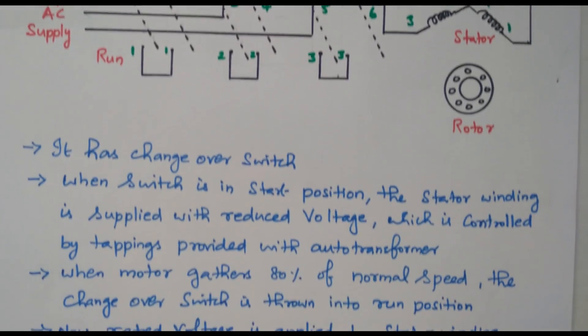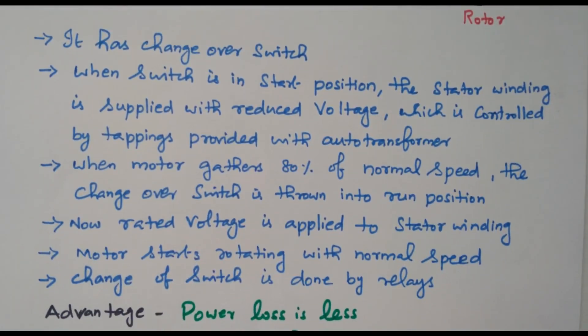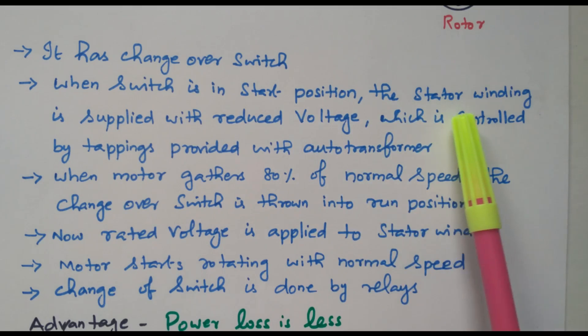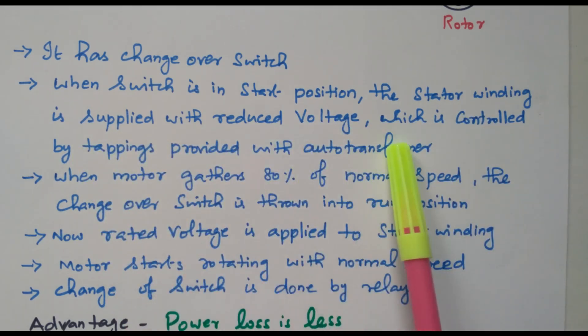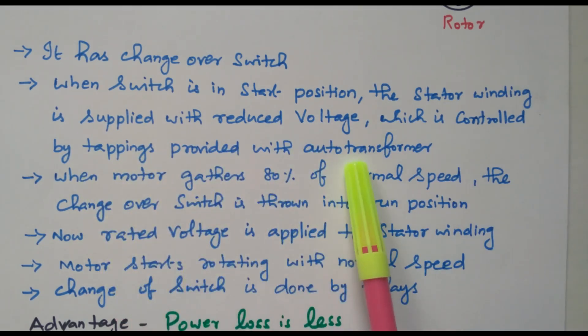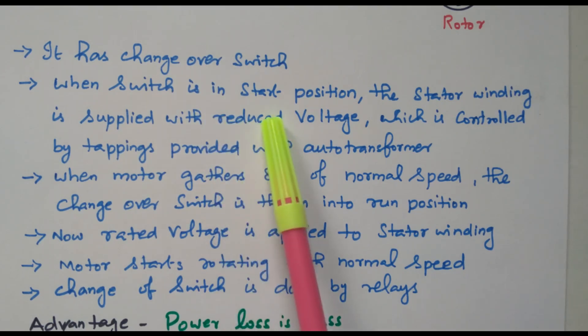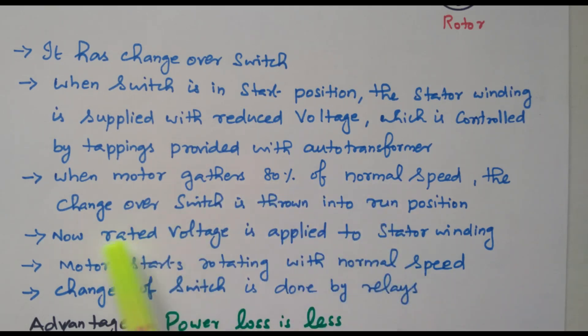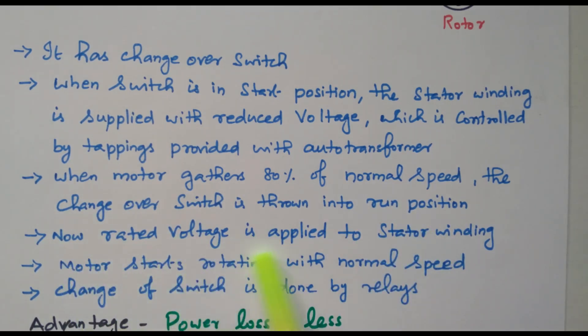Now we will see the description. There is a changeover switch. When switched to the start position, the stator winding is applied with a reduced voltage, which is controlled by the tapping provided in the auto-transformer. When the motor gathers 80% of normal speed, the changeover switch is thrown into the run position, meaning the entire voltage is applied. Now the rated voltage is applied to the stator winding and the motor rotates at normal speed. The changeover switch operation is done by a relay.